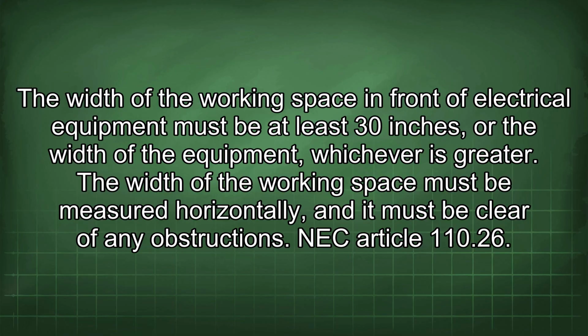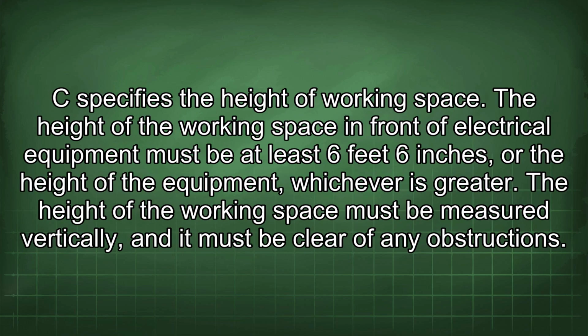NEC Article 110.26 C specifies the height of working space. The height of the working space in front of electrical equipment must be at least 6 feet 6 inches, or the height of the equipment, whichever is greater. The height of the working space must be measured vertically, and it must be clear of any obstructions.